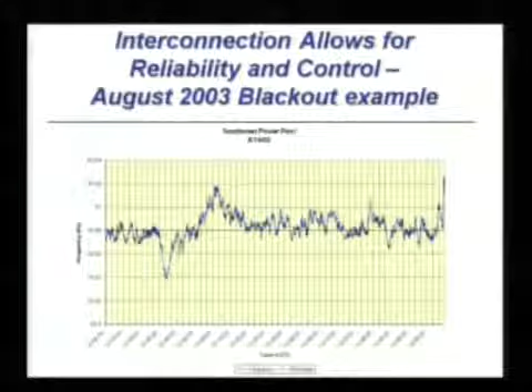So what happened is your supply went away, but your load was still there. So the system starts to slow down. Well, so the Eastern Interconnect starts to respond and the frequency starts to pick up. Well, then bam, right about 12:55 or so, the Northeast went black. So 50 million customers in the dark, and now you have oversupply, and so the frequency overshoots, and it takes it a while to go back down.